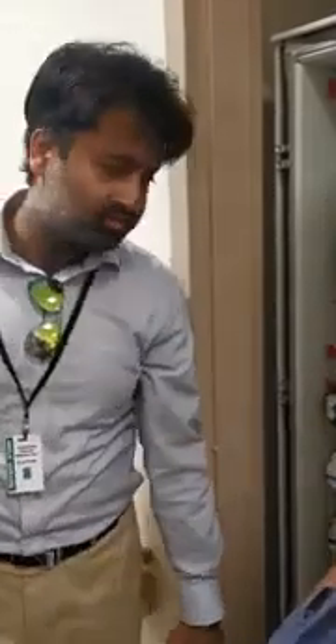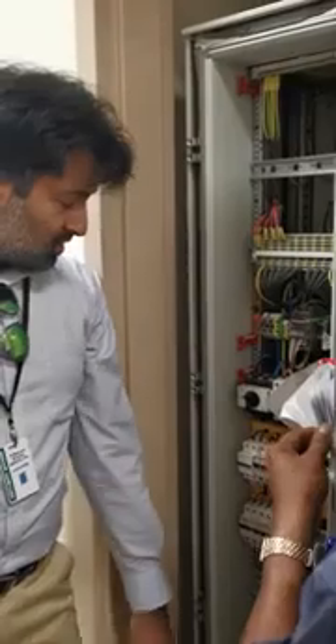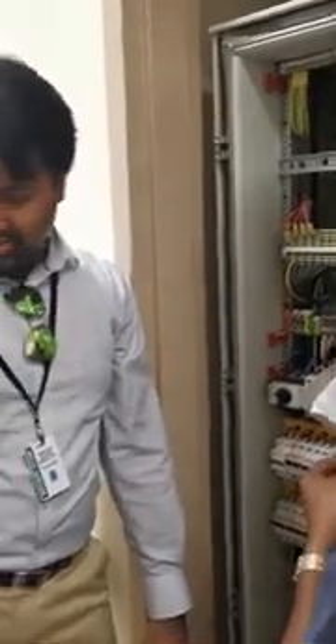So at that time you need to check whether it is a real temperature rise, or the fan got damaged, or something is wrong with the thermostat. These are the things that need to be checked at that time. So these are the three major alarms that you need to simulate and check. I don't know if there is anything else in your list, or that's all. Yeah, I have one.